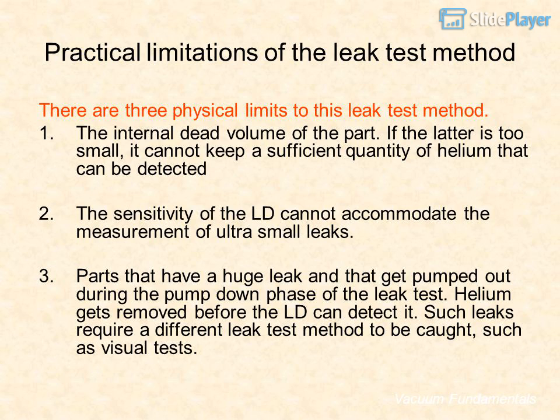3. Parts that have a huge leak and that get pumped out during the pump down phase of the leak test. Helium gets removed before the LD can detect it. Such leaks require a different leak test method to be caught, such as visual tests.